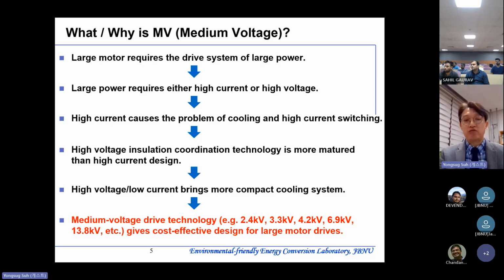This medium voltage drive technology is usually classified from 2.4 up to 13.8 kilovolt. To my best knowledge, medium voltage drive systems above 13.8 are not available because of the lack of semiconductor devices, unless we use series connection of multiple devices. But series connection is not always feasible because you cannot share the voltage equally.